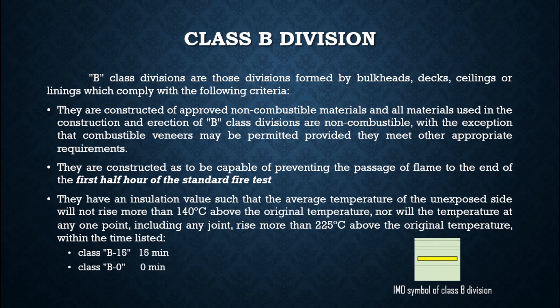Class B divisions must have an insulation value such that the average temperature of the unexposed side will not rise more than 140 degrees Celsius above the original temperature, nor will the temperature at any one point including any joint rise more than 225 degrees Celsius above the original temperature.